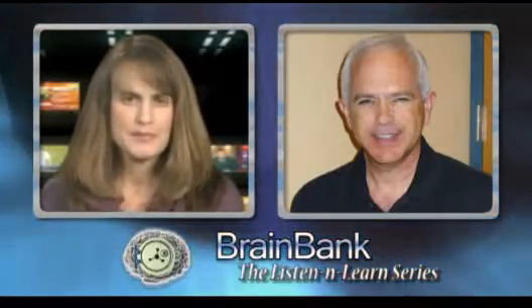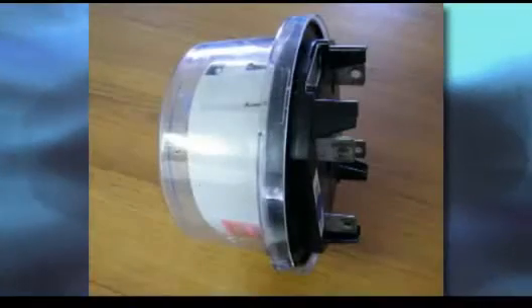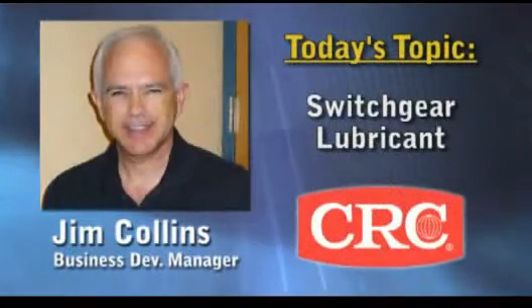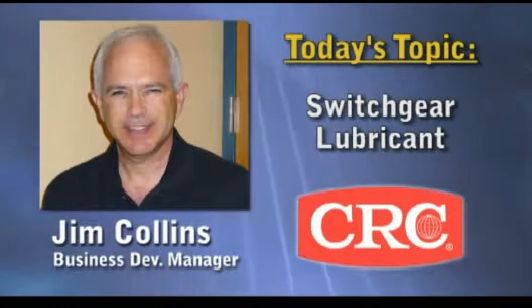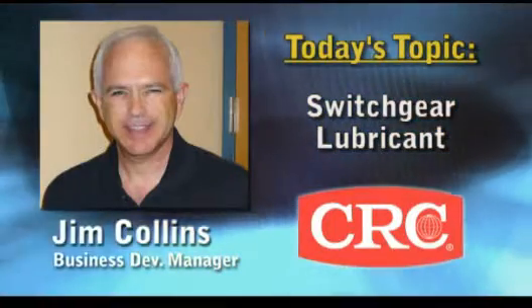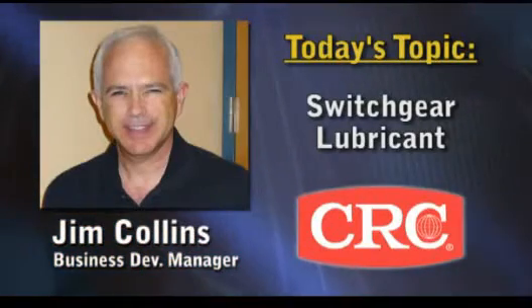Describe what kind of equipment this product is typically used on. Well, there are two main applications. Switchgear, or distribution disconnect switches of all kinds and types, and then metering — meaning all types of the new AMI or AMR plug-in systems, including smart meter programs. When faults occur in the line or maintenance is needed on the switch or meter, these products should quickly and safely open. They can reroute power, disconnect the circuit, and utility crews then use that to make needed repairs down the line. Or a meter can be pulled out for service. We do that with the right kind of lubrication.